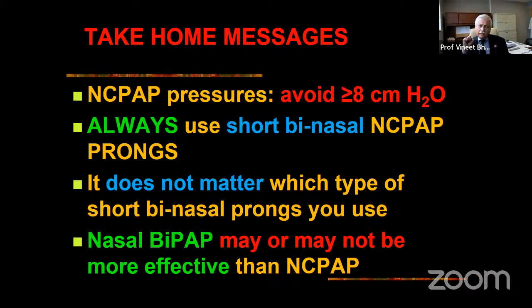Highly recommend use short binasal CPAP prongs. Do not use long prongs. Mask you can use, but make sure the fitting is appropriate. When you use longer prongs, resistance in the circuit is directly proportional to the length of the tube and inversely proportional to the fourth power of the radius. I'm sure you know this physics, right? But if you use the nasopharyngeal prong, if you look at the caliber, it actually starts off like this and then it narrows down. So you can imagine the length is contributing to resistance, plus the fact that it's decreasing the caliber of the diameter of the nasopharyngeal prong, that will increase the resistance.